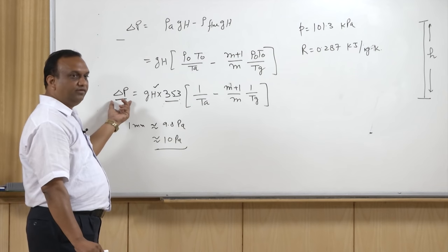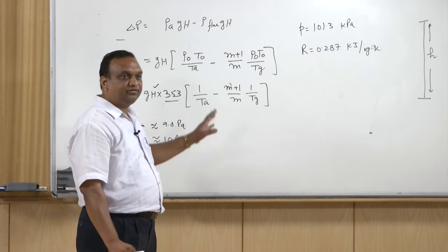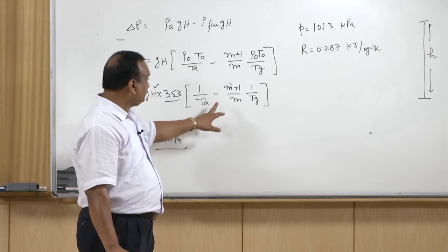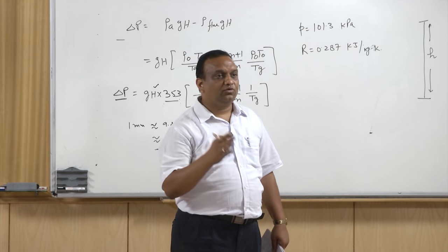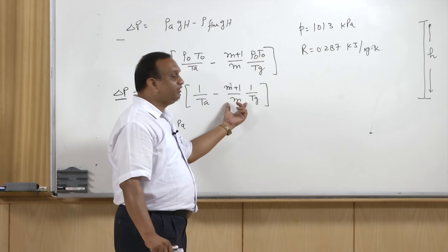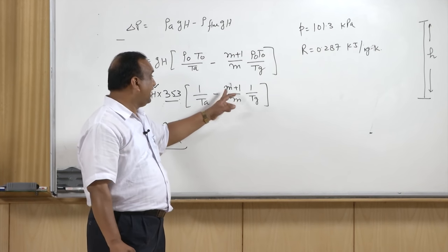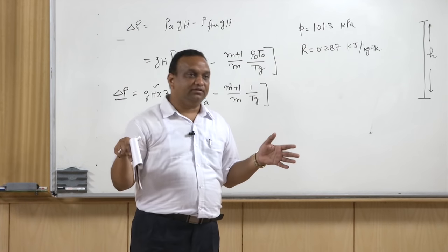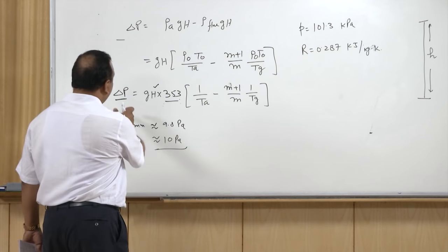This expression gives the draft developed in a chimney of height H as a function of T_G, T_A, and the ratio (m+1)/m. If identical boilers are added or more fuel is burned, this ratio remains the same, so the required chimney height stays constant for the same pressure difference. Only the cross-sectional area of the chimney increases to accommodate more flue gases.